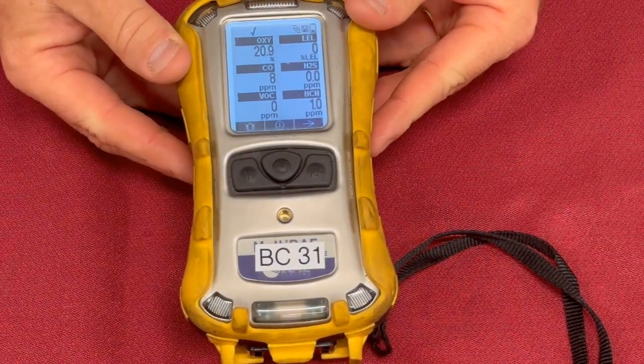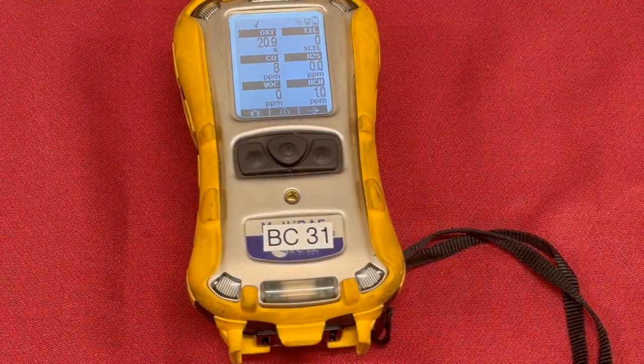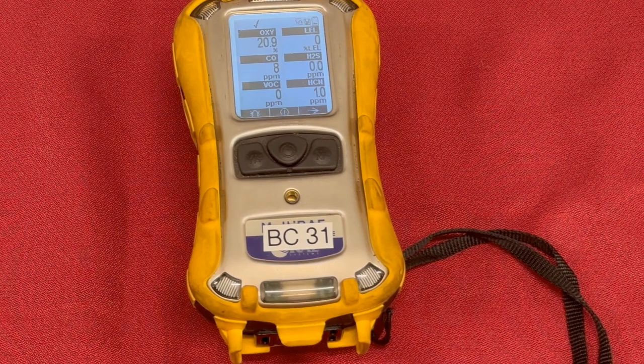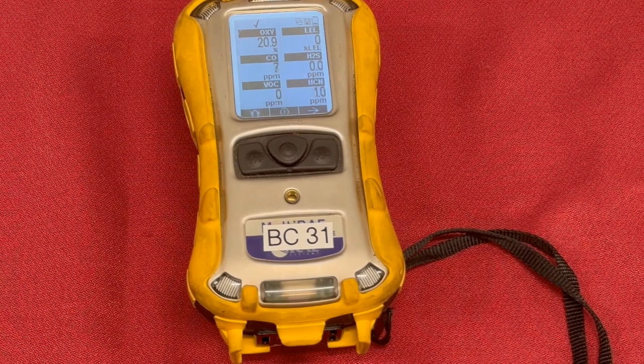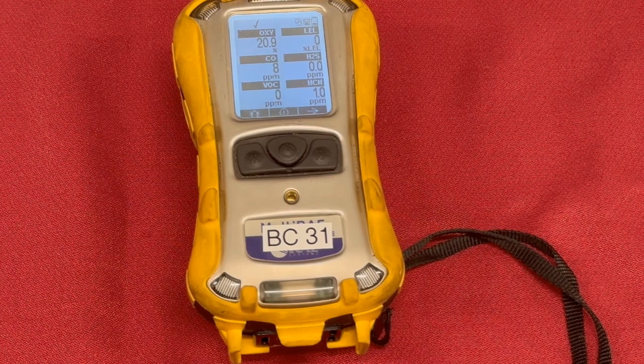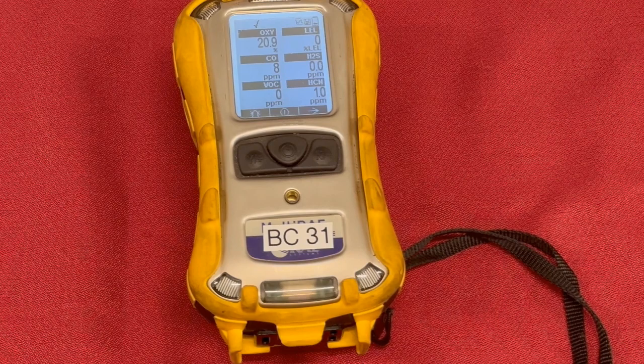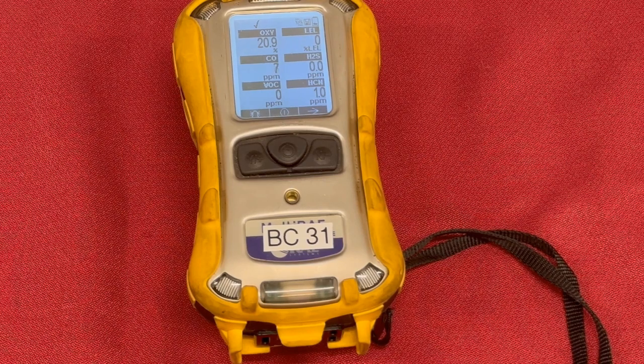VOC is the reading in parts per million from the PID, the photoionization detector. There is a list of products that this measures. It measures any volatile organic compound. There's a list of about 8,000 different things it measures. It's measuring them in relation to isobutylene. It thinks that isobutylene is what it's looking for. We use our conversion charts to figure out the exact exposure limits.